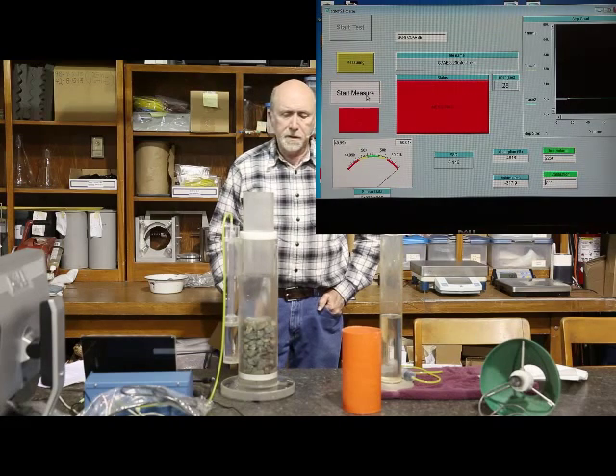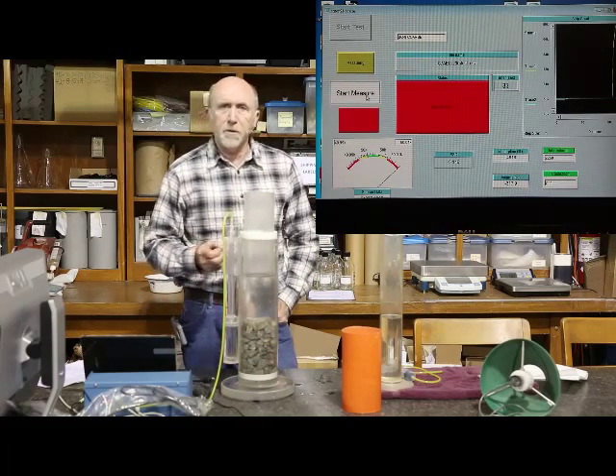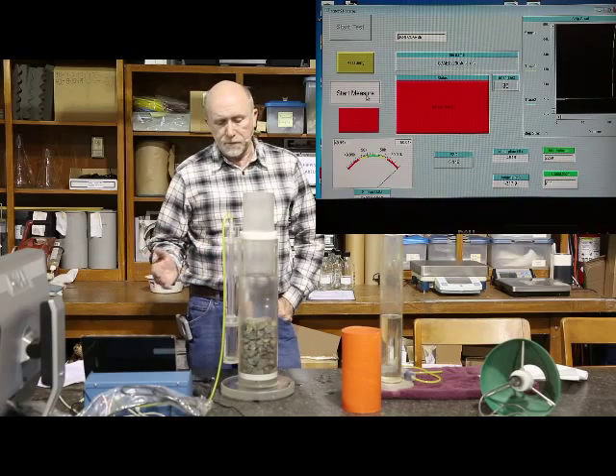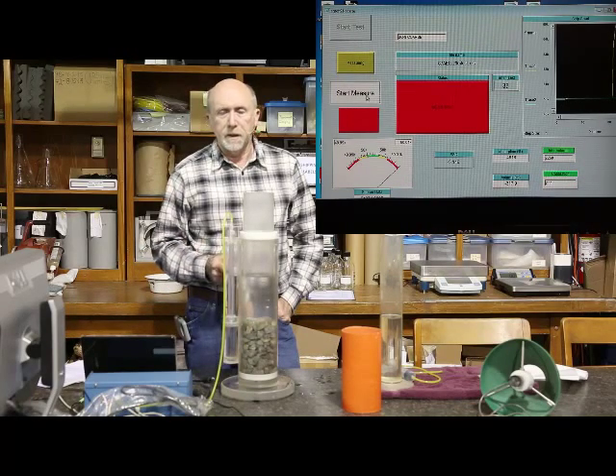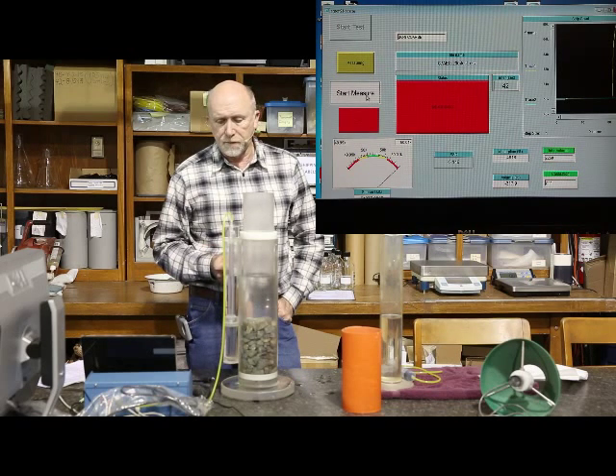Now the system is going to take a measurement which will give us a displacement, which will give us the bulk specific gravity. Then it will continue measuring for the next several minutes and take another measurement which will tell us what the absorption values are for this aggregate.